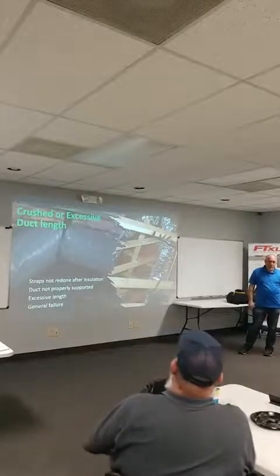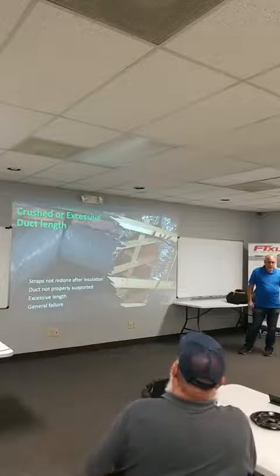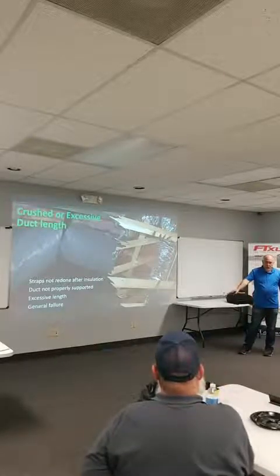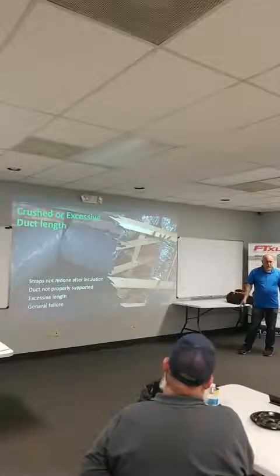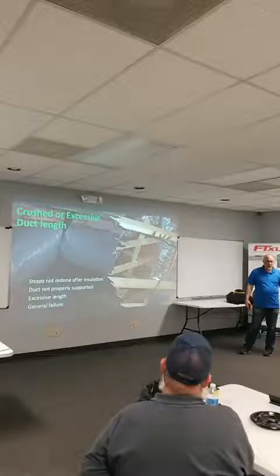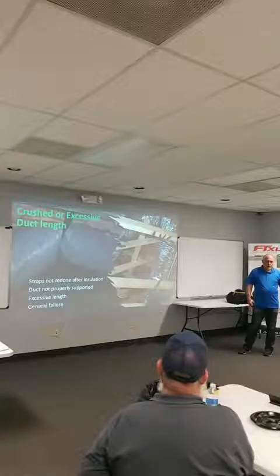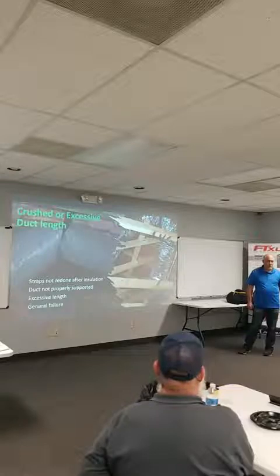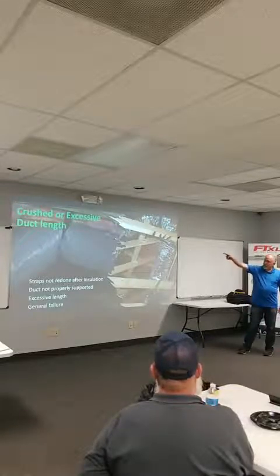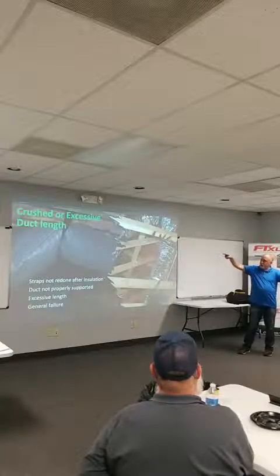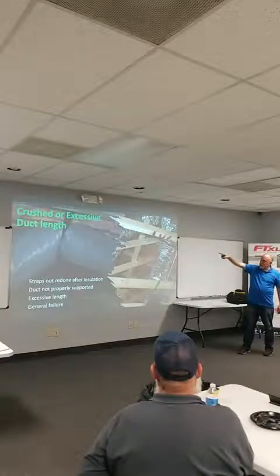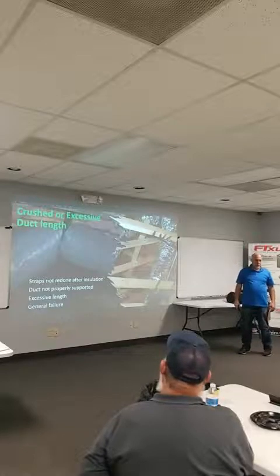So then we go down to the downstairs unit. I just walked down there and I'm putting my hand in front of the registers. I'm like, did you guys ever check the air coming out of the registers? And they're like, well, no, we don't want to walk around the house. I'm like, well, you're having problems with cooling the house. Don't you think you should really check and see how much air you got coming out of the registers? They go, well, they're fine. We put the ductwork in. They had a company come in and insulate the house. The insulators pulled the ductwork down to get the insulation bats up behind it and choked off their ductwork, right?